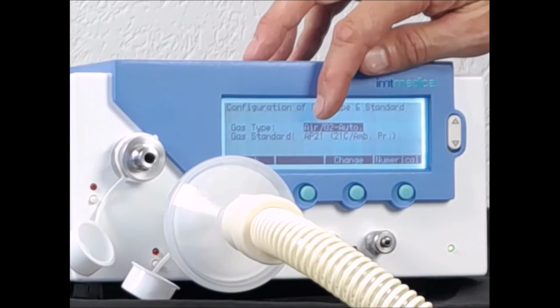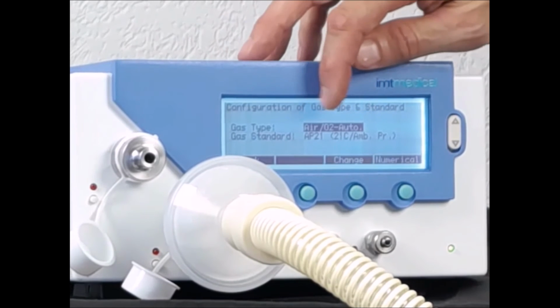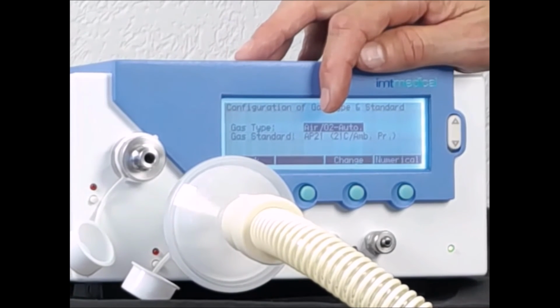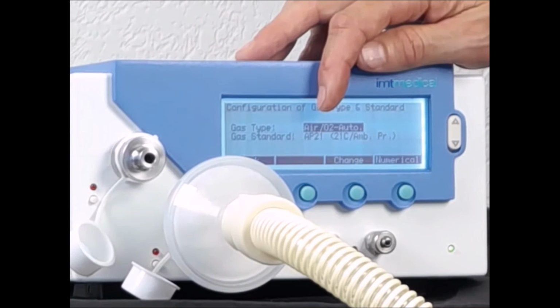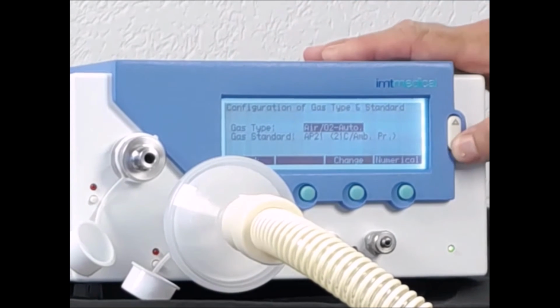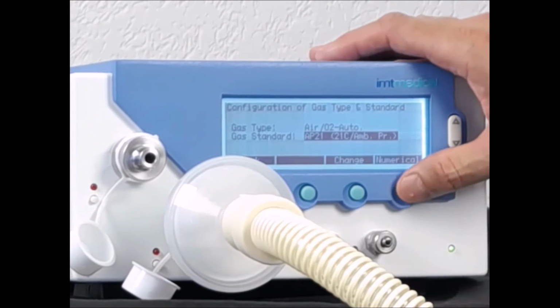Then the gas standard is AP21. AP21 is used for the Bella Vista ventilator. Any other ventilator may have a different gas standard, and the only way to know which gas standard to set is by reading the service manual of the ventilator or the anesthesia machine. So both are matching up.